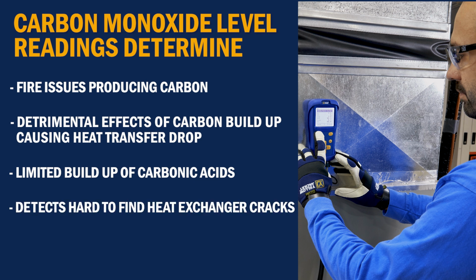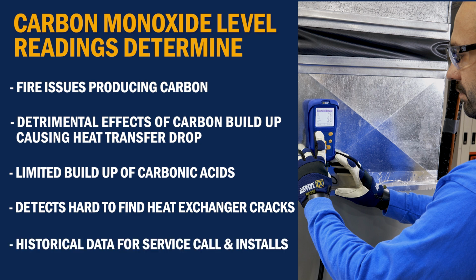It can also help detect cracks that are hard to find in your heat exchanger without having to pull apart your entire furnace. Checking each new install makes sure it is installed correctly and gives you historical data to check against on the next visit.